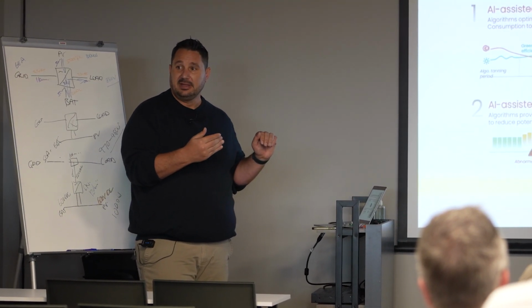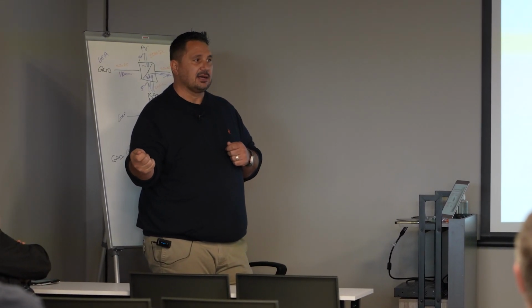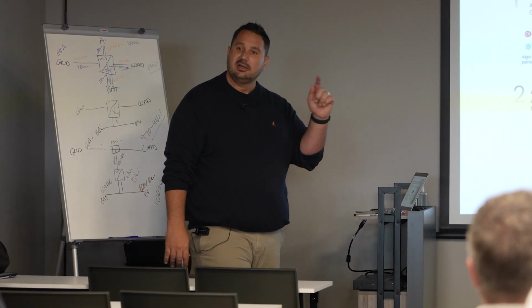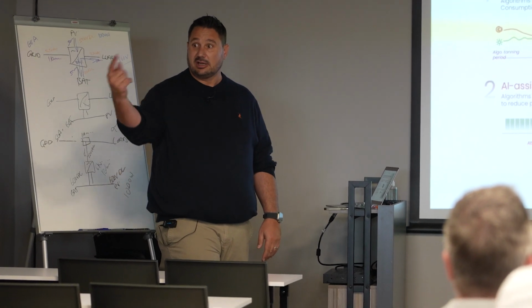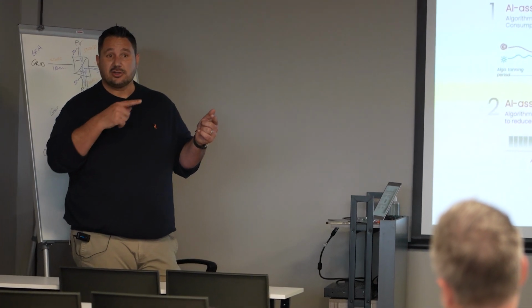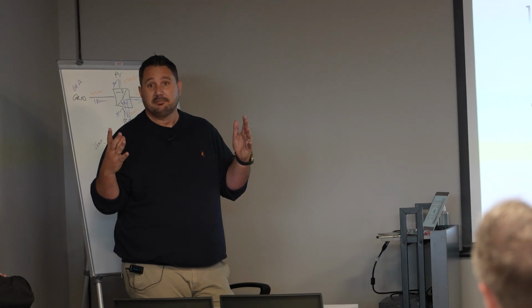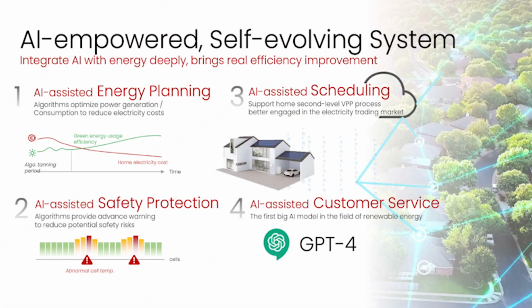It also has the ESP app plugged in, so while we're using batteries for arbitrage - buying at low rates, selling at high rates - if Eskom announces stage 4 and power will be off in 2 hours, the system sees the current load is 20 kilowatts, and based on learned patterns, expects it to peak to 30 kilowatts within those 2 hours. So it calculates it needs at least 60 to 70 kilowatt hours in the batteries, and charges them at the right rate over those 2 hours so it's ready to switch over when load shedding hits.